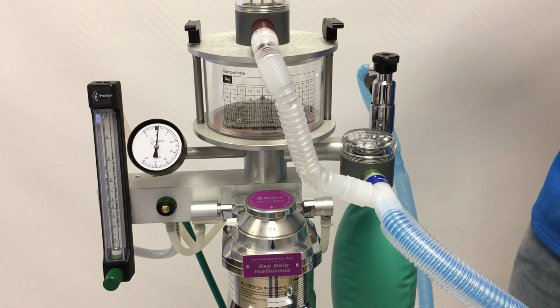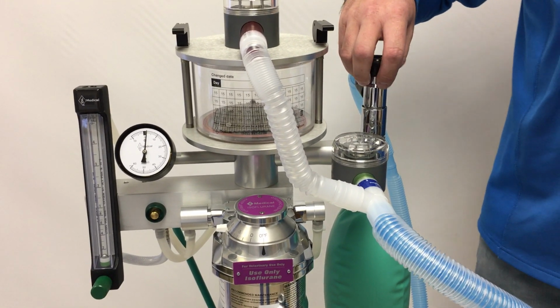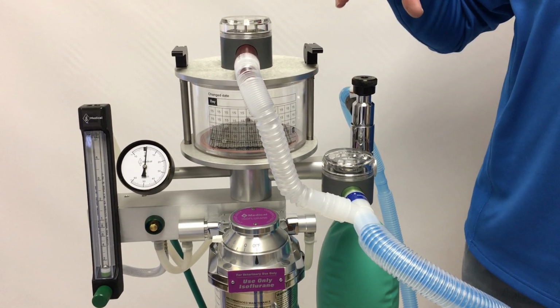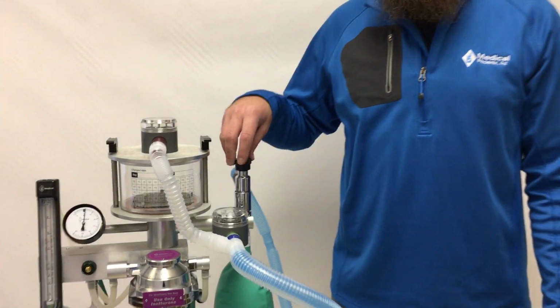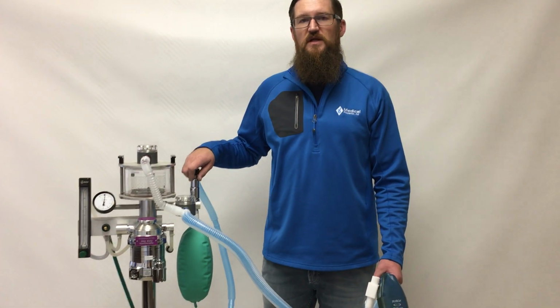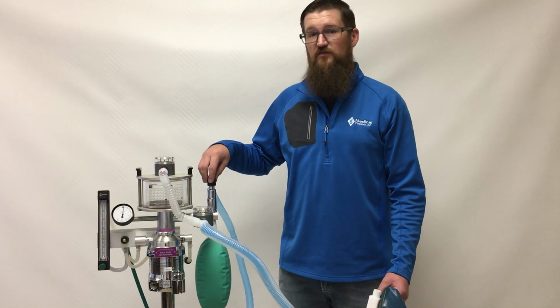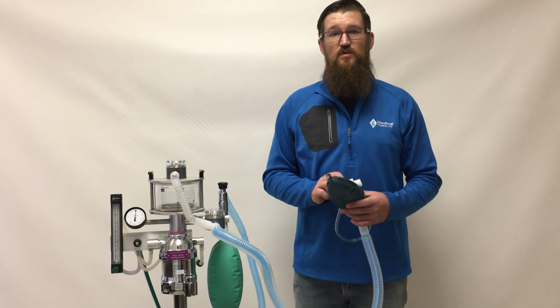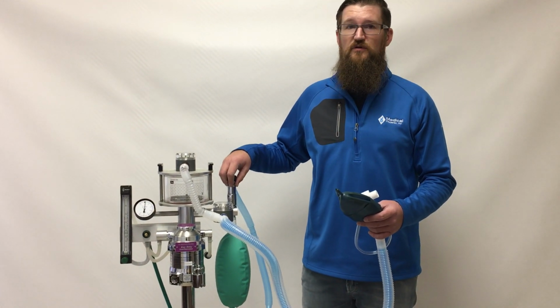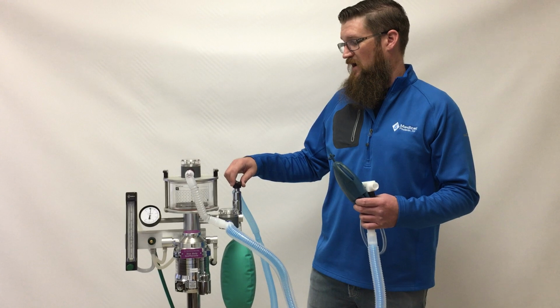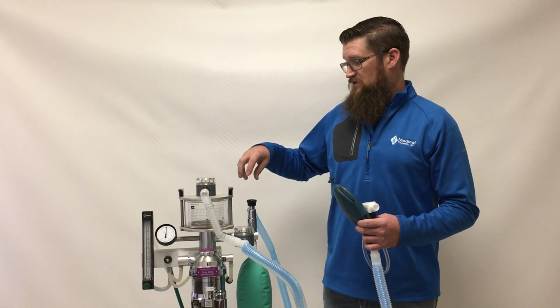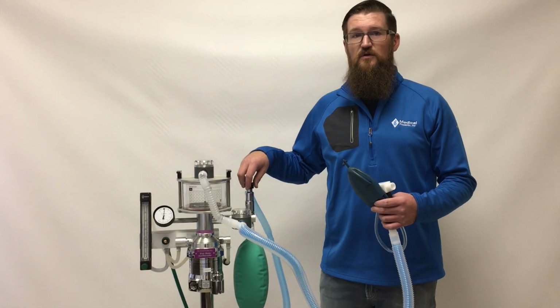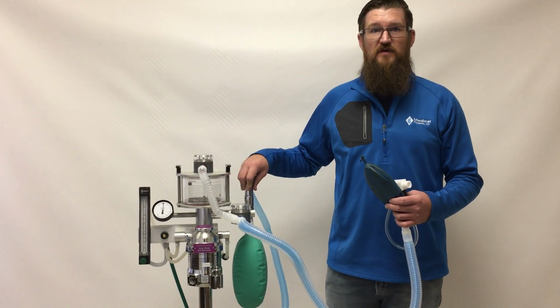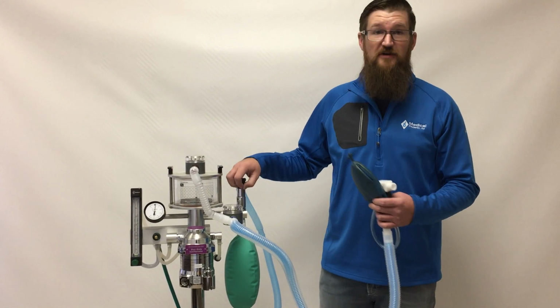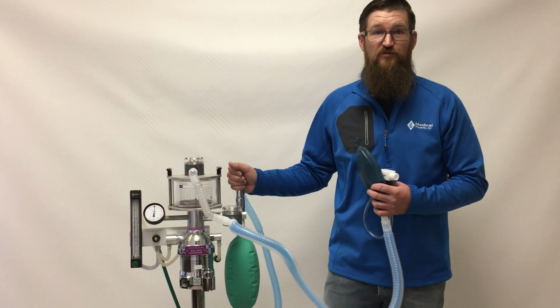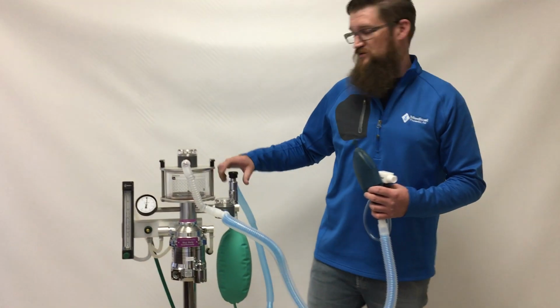Many hospitals will have policies that say that the pop-off valve is never to be closed. That is a good policy that will increase safety, but it doesn't eliminate the possibility of accidental closure, equipment malfunction, or a service mistake where a service company may come in to do a pressure check during a yearly preventive maintenance or just an anesthesia machine repair and accidentally leave the valve closed. So accidental closures and equipment malfunctions are not going to be eliminated by a policy of leaving the valve open, or even in certain circumstances taping the valve open or fixing it so that it won't physically close. Service companies are certainly going to be closing that.